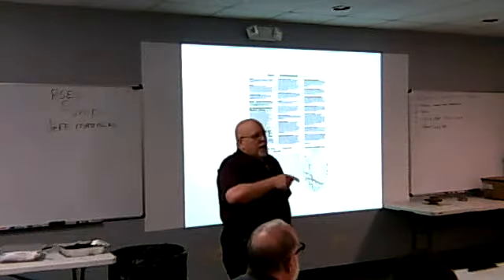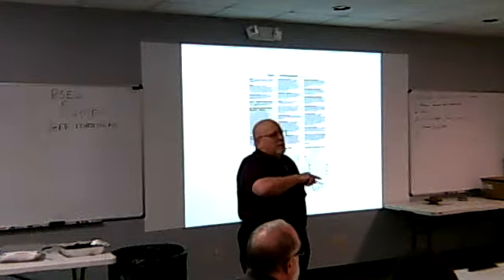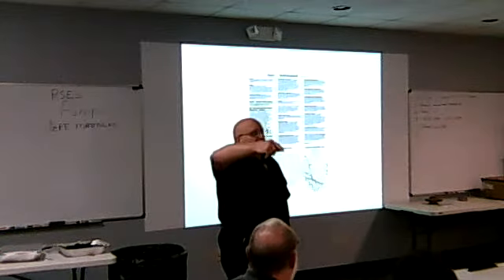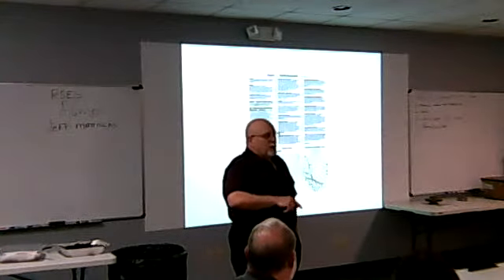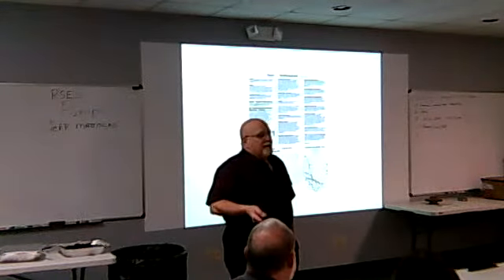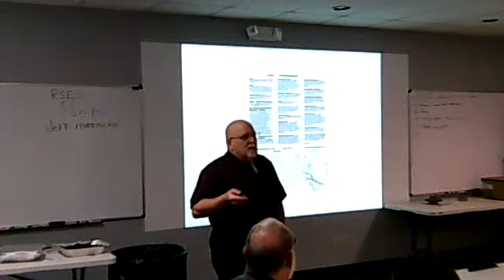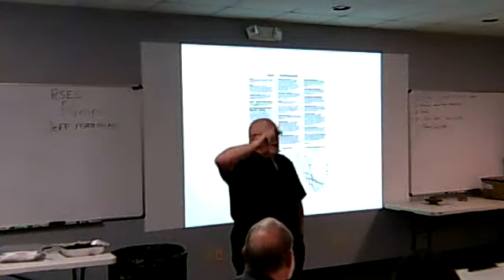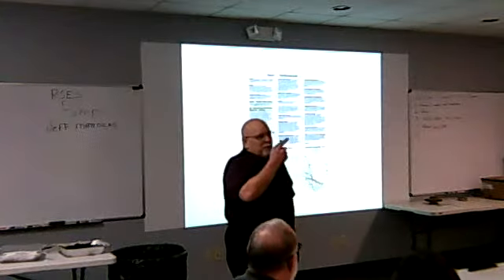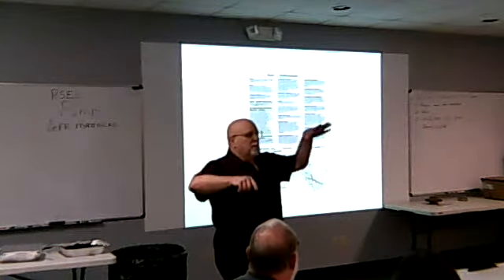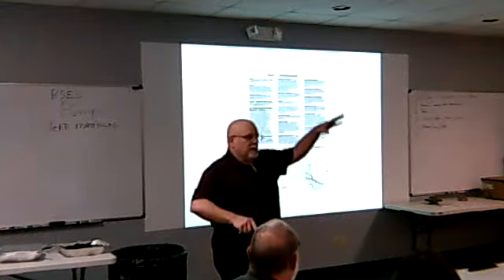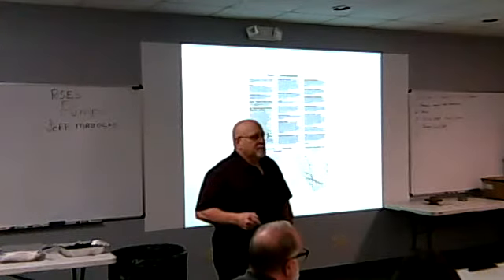It's closed, you set your fill pressure, take the elevation, if it's 23 feet, divide by 2.31, it's 10 PSI. That's your fill pressure. That'll give you positive pressure on the top. And then your pump will take over from there. Because it's equilibrium on both sides. When it comes up, pushing down. Any questions on that?